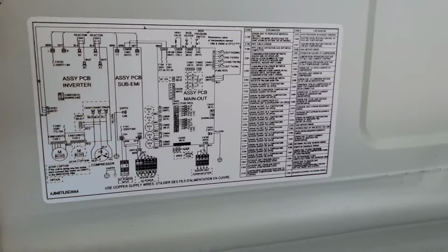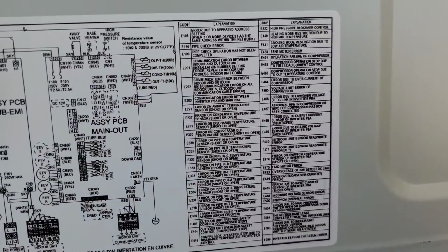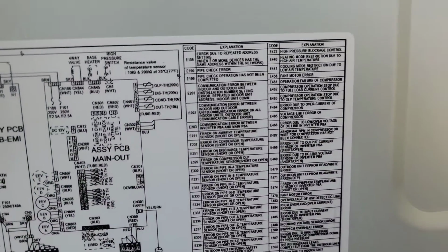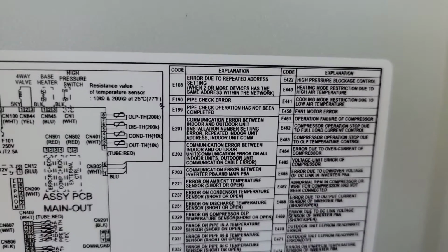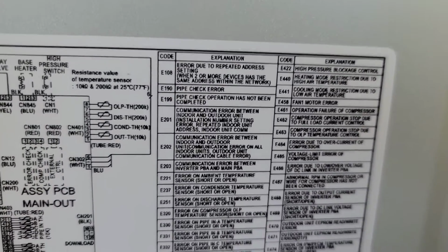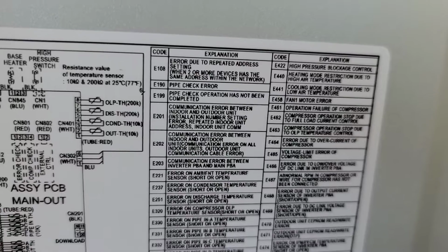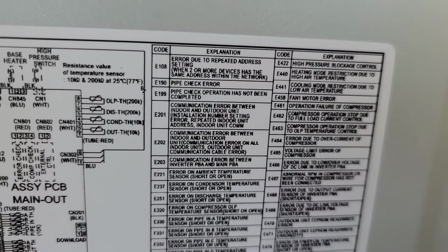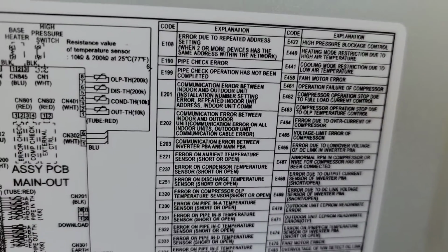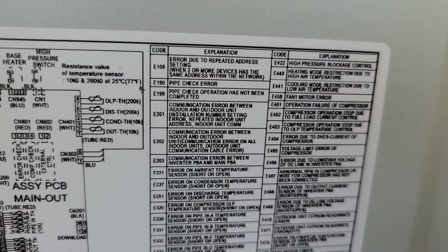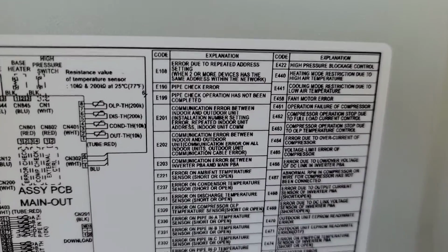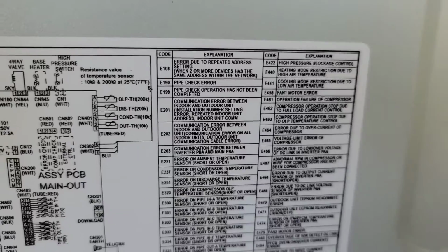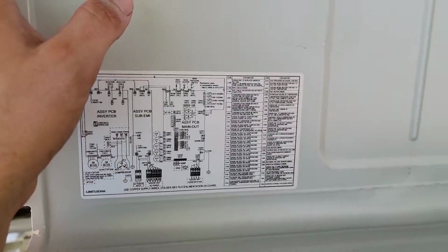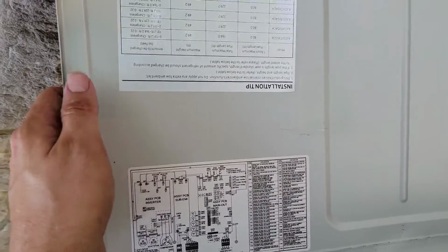So we have our panel here, and if we just flip it around, we have a diagram that says E108 at the top. Error due to repeated address setting when 2 or more devices have the same address within the same network. That means you might have to use the controllers inside to address, and that can be found in your user manual, your user guide, your installation guide.